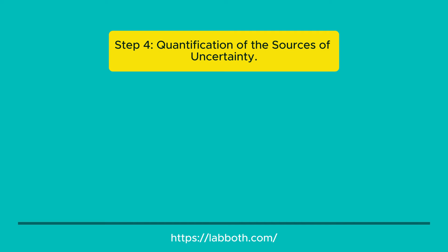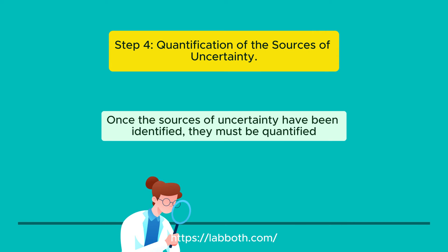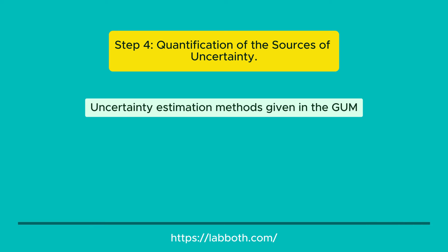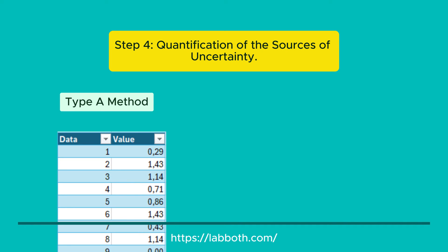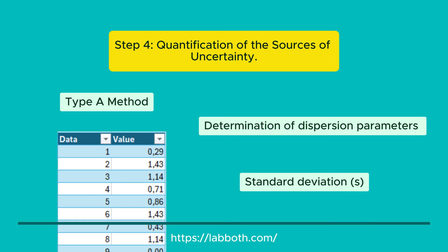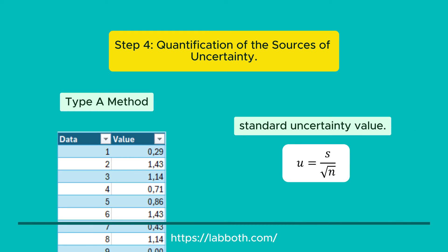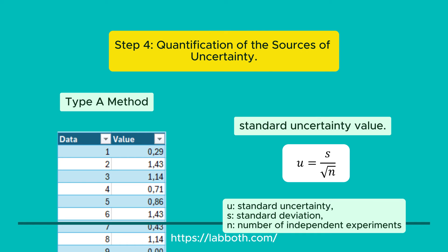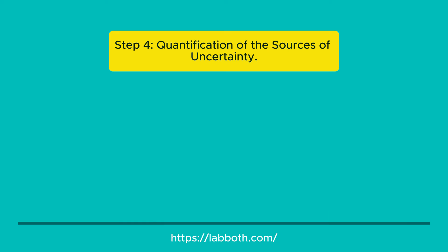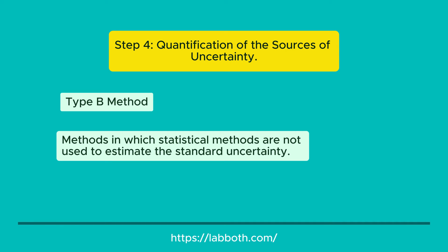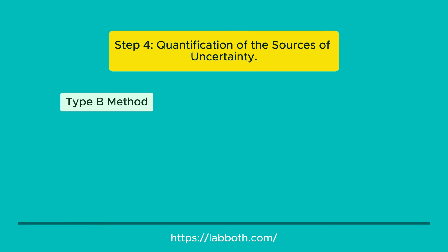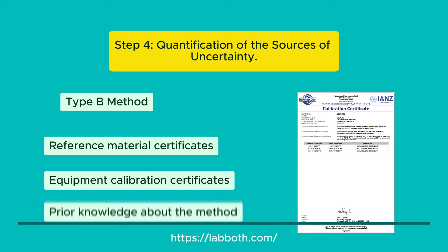Step 4: Quantification of the Sources of Uncertainty. Once the sources have been identified, they must be quantified using the uncertainty estimation methods given in the GUM guide: Type A or Type B. Type A refers to estimation through statistical methods — for example, collecting data under repeatability conditions and determining dispersion parameters such as standard deviation. Apply the formula U = S / √N to obtain the standard uncertainty, where U is standard uncertainty, S is standard deviation, and N is the number of independent experiments. Type B considers methods not based on statistics, such as reference material certificates, equipment calibration certificates, and prior knowledge about the method.